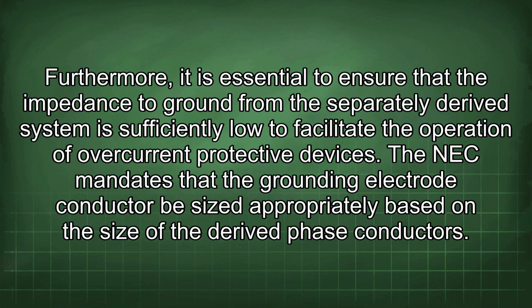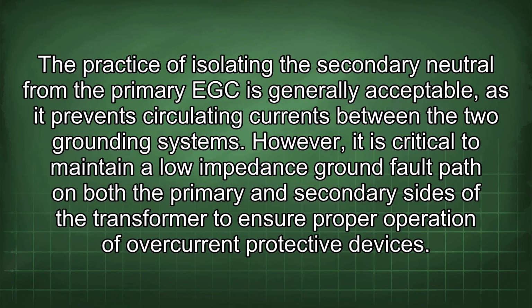Furthermore, it is essential to ensure that the impedance to ground from the separately derived system is sufficiently low to facilitate the operation of overcurrent protective devices. The NEC mandates that the grounding electrode conductor be sized appropriately based on the size of the derived phase conductors. The practice of isolating the secondary neutral from the primary EGC is generally acceptable, as it prevents circulating currents between the two grounding systems. However, it is critical to maintain a low impedance ground fault path on both the primary and secondary sides of the transformer to ensure proper operation of overcurrent protective devices.